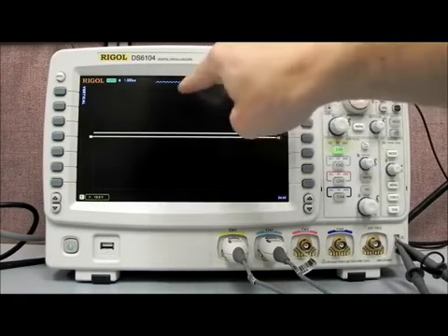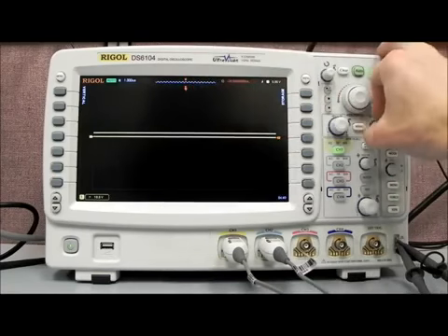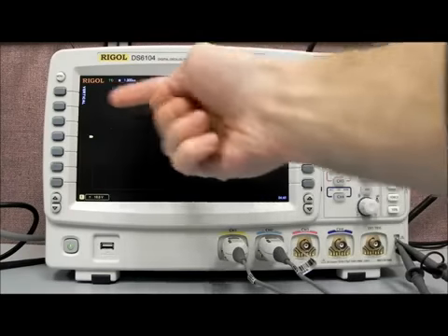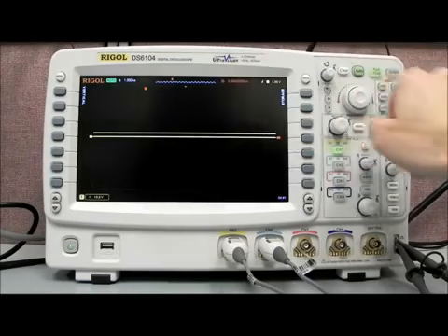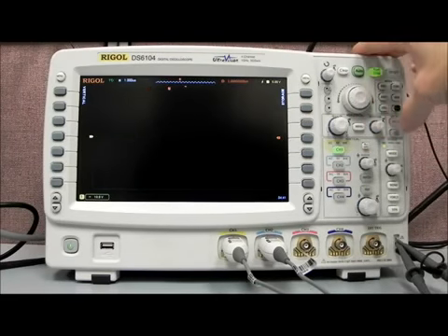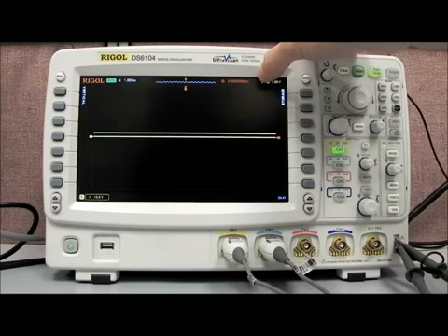The D denotes the distance in time from the trigger point to the actual center point of the display. So you can see as we go counterclockwise, we're actually going in negative time, what's called the pre-trigger area. And if we go the other way, we're going to post-trigger time. Again, this is the trigger, so these are events that have happened after the trigger, and so we'll see we have a positive time-based offset. To get back to center, you can just press the small position knob and it will bring it back into the center point.